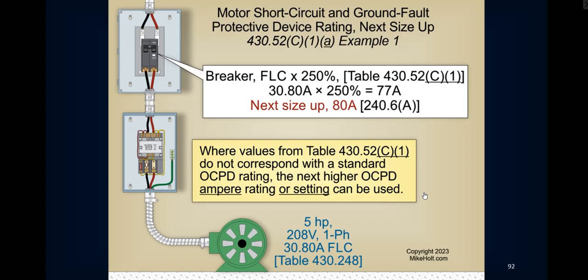it was. Yeah, 250%. So you went and taken the FLC from the NEC, you went to 430.248, and that motor pulls 30.8 amps times 250%. So now it's 77 amps. So now we've got the next size up per 240.6A, which is your standard ampere ratings. That means I'm putting an 80 amp breaker on a 30.80 amp load. So where the values from 430.52 do not correspond with the standard OCPD rating, the next higher OCPD ampere rating or setting can be used.